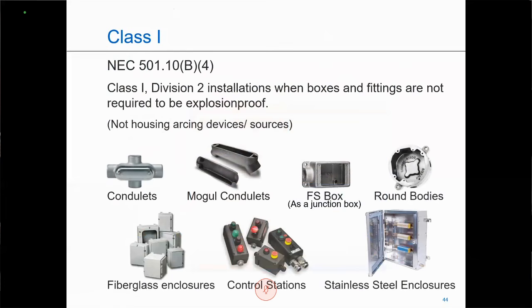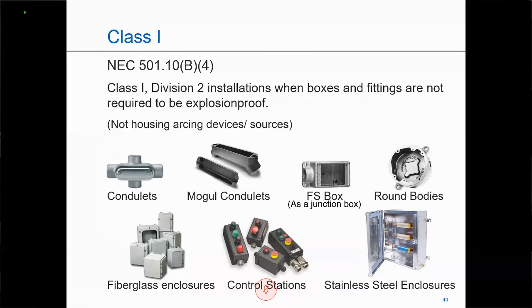And in the end, what it means is that in those particular applications in Class 1 Division 2, you might see the everyday conduit body used, or you might see enclosures that are non-rated NEMA 7 enclosures used. That could be enclosures just designed for the environmental protection. You might see terminals inside. You might see FS boxes just being used as splice boxes.